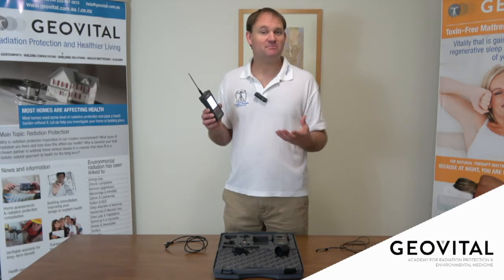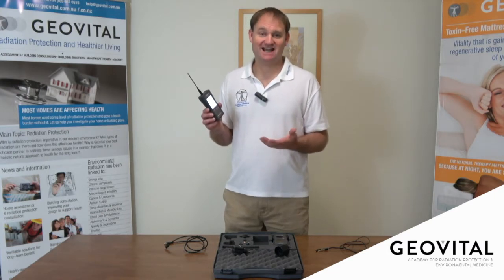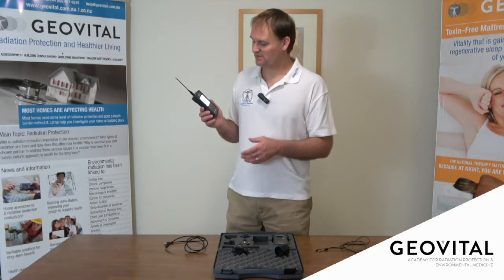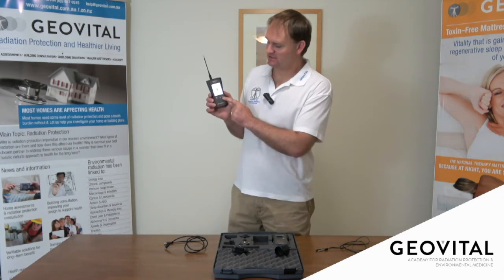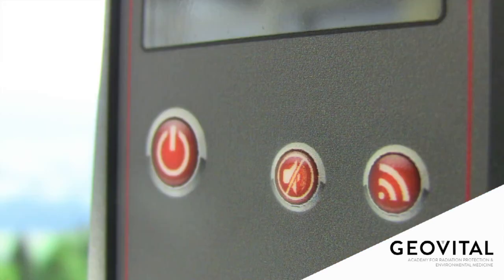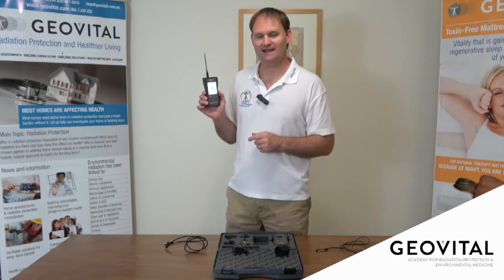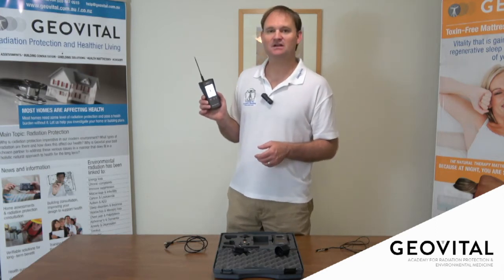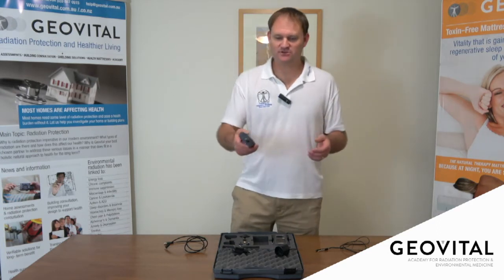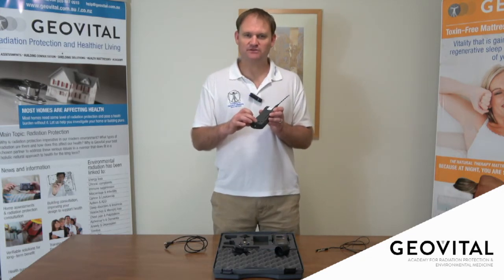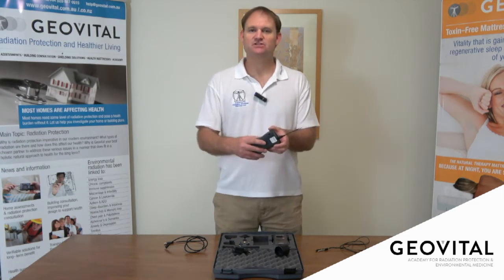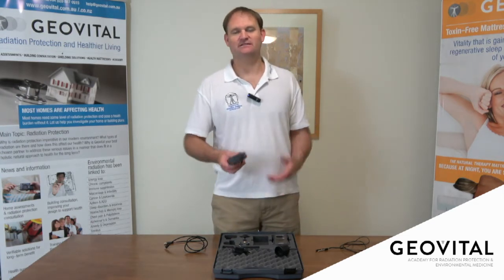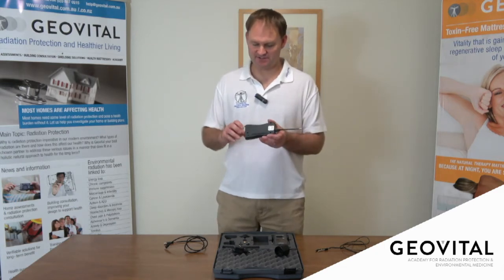Now, this beep, beep, beep alarm can be deactivated. The Geiger counter sound cannot be deactivated. To turn off the alarm, you press the middle button, a little speaker icon with a little stripe through it. This turns off or turns on the beep, beep alarm put over the top once it passes 100. The Geiger counter sound can be turned down, as I mentioned. So if you're mid-measurement or mid-assessment and you want to talk about this, let's say, the volume, the sound comes out of the little hole at the back. So if you just slide your finger onto the little hole at the back, then the sound is very dampened.